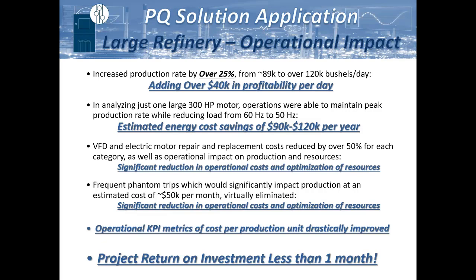Their VFD and electric motor repair and replacement costs, for VFDs, it was actually over a 70% reduction. And on their motor repair and replacement costs, that went down by about 60%. So all of these had a significant impact on the overall production rate, efficiency, and costs of the facility. It instantaneously became the most profitable and the highest producing plant throughout the entire organization. Since then, we've been doing mass implementation at all their facilities because they see tremendous impact.